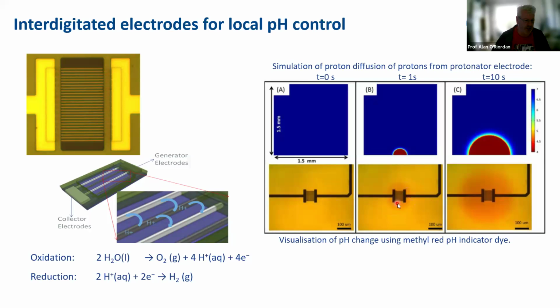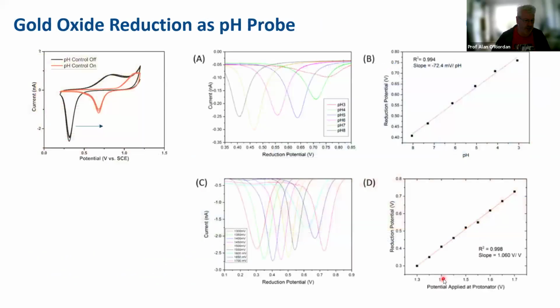So within this red zone, we've changed the pH environment. We've dropped it from what was initially pH 7 down to pH 4.3. And as the time moves on, you can see this red circle spreading out even further. So we can temporally and spatially change the pH around the sensors. So we can, in theory, and we've shown this, have multiple different sensors measuring different things in the same sample, and each one of those sensors is measuring at different pHs. So that really allows us to do pH control. And now all of this work was enabled by the simulation tools to inform us on what the best type of design should be.